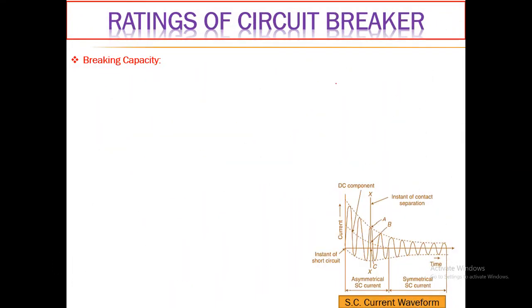Here I have shown a waveform representing the short circuit current. The waveform has an asymmetrical shape. The fault current comprises two components: one is the AC component, which is sinusoidal, and the second is the DC component, which arises due to the inductance of the line. The DC component decays to zero, after which the waveform achieves a symmetrical shape.